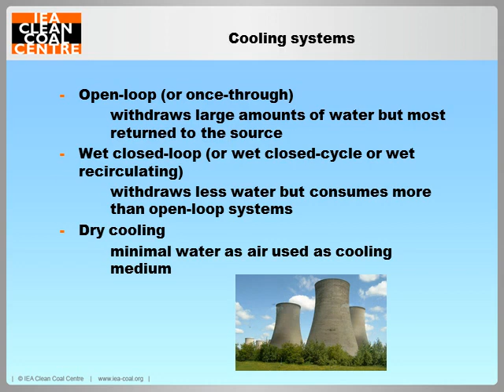This figure compares water withdrawal and consumption ranges per unit of electricity for a number of thermal power generation technologies fitted with different cooling systems. I just want to point out that fossil fuel and nuclear power plants with once-through cooling systems, shown at the bottom of this figure, have the highest water withdrawals per unit of electricity generated, but they are amongst the lowest for water consumption. It's the combined cycle gas plants which have the lowest water withdrawal and consumption rates among the thermal plants with similar types of cooling systems.